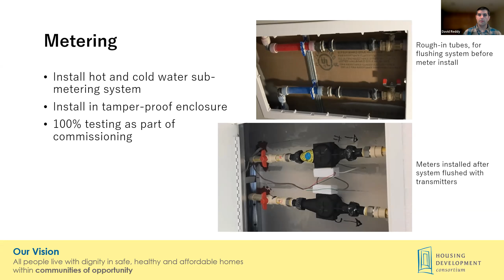But what we have learned in helping teams implement metering and commissioning is that the meters are only as useful as they work and are reporting the data accurately and in the right units. Unfortunately, with the flurry of things happening at the end of a construction build, metering is oftentimes not number one on the owner's mind. If this isn't followed up on to make sure it's been commissioned properly, it's really hard to determine if there's a problem later without going into every unit and doing a lot of testing.